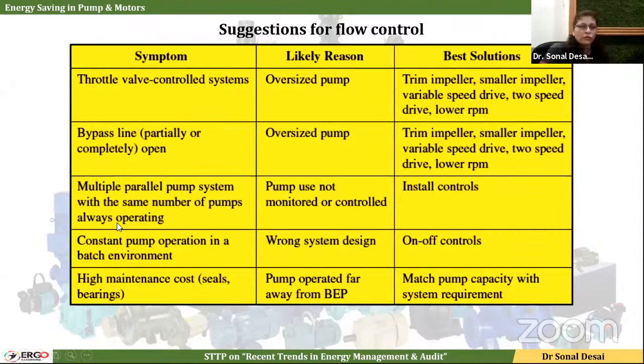If you find that multiple parallel pumps are there and the same number of pumps are always operating, then it signifies that pump use is not monitored. Use the control, it can be on-off control, it can be sequencing control, and according to the requirement, operate them. Same way, when there is constant pump operation, then again, you need to monitor those things. If the pump is frequently failing in terms of seals or bearings, then again, it is an indication. Also, if there is vibration, then again, it is an indication that the pump is not operating at its best performance. It is operating very far away, and we can match by redesigning the operating conditions. So this is a very important slide for those who are looking for a remedy in an existing pump.